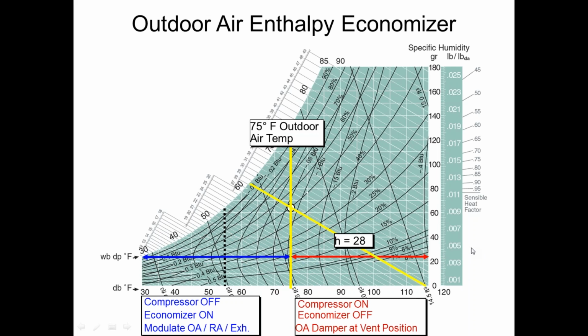All right, so expanding on that, if I do the enthalpy version, then instead of that vertical line, I'm following these enthalpy lines. So these are my enthalpy lines over here on the psych chart, if you didn't know that. All right. If I find 28, it's right here. I draw my line down. Boom, I'm good there. But I don't really want a dry day where it's 100 degrees. That's not really going to work for me. So I have the 28 enthalpy number, and I have the 75 degree temperature cutoff number.